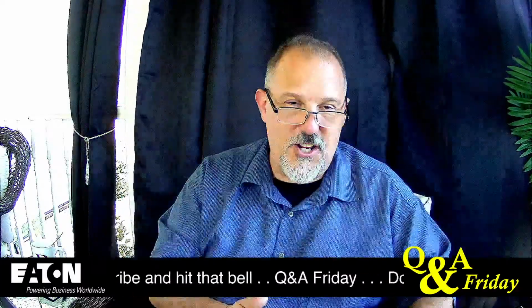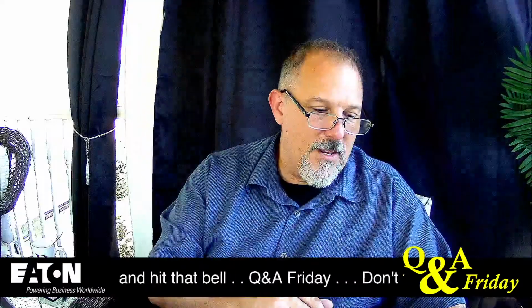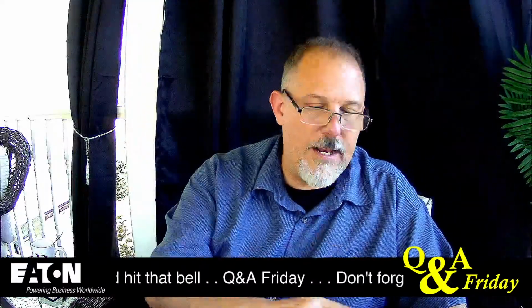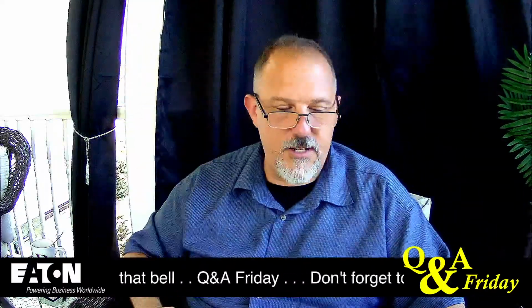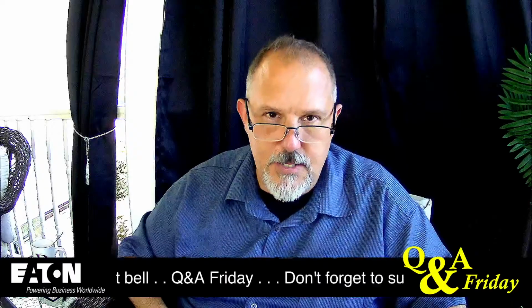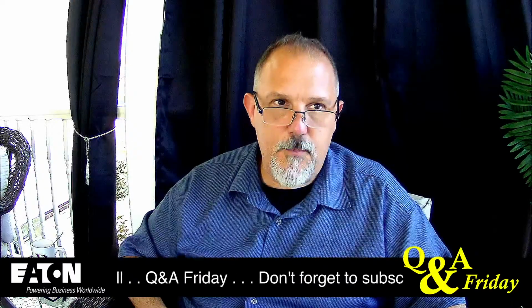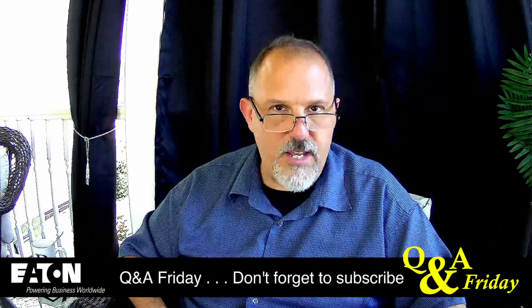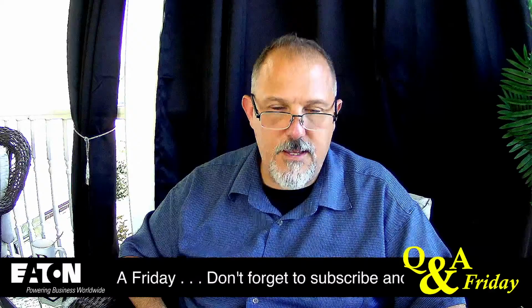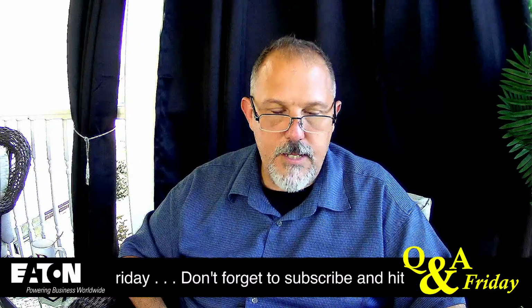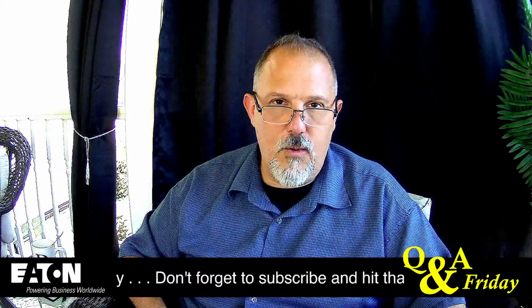250.24C. So this individual said, and I wrote a nice little email, and this individual came back and said, you had me up until you have to pull the grounded conductor, the neutral, even if you're not going to use it, to that fire pump. And they said, why?